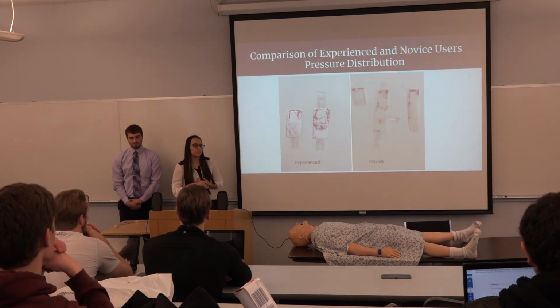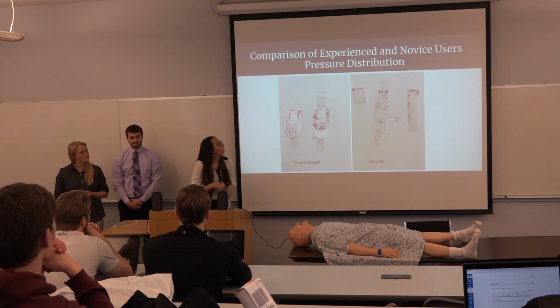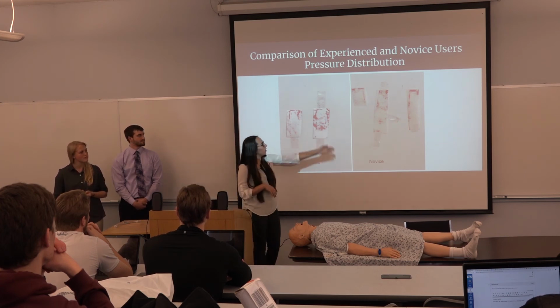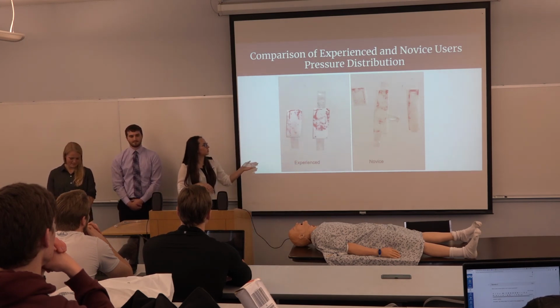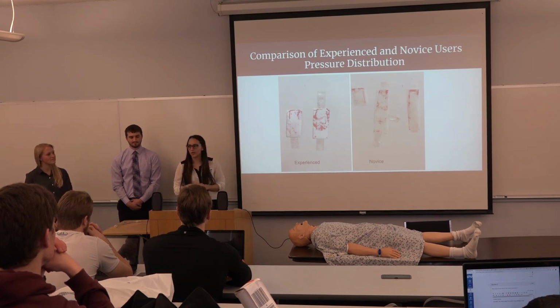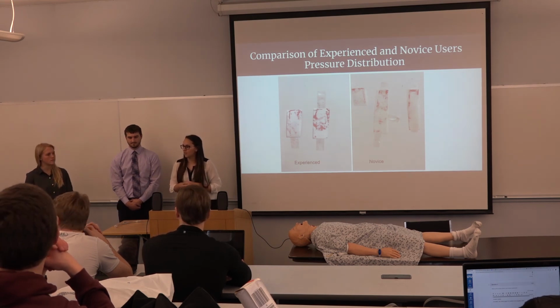We defined experienced as professionals that have done 10 or more intubations on live patients, and novice as people that had less than that. We found a trend that the novice users had more pressure at the end of the blade, especially near the tip, and the experienced users distributed the force more over the whole area. And you can see that on our 3D printed blade, just a mock of one of the tests we did.